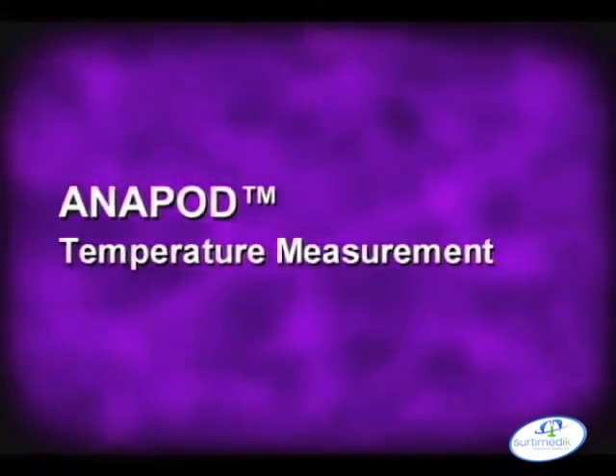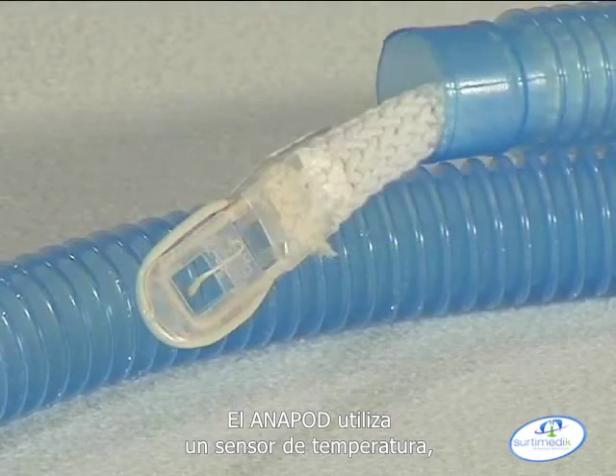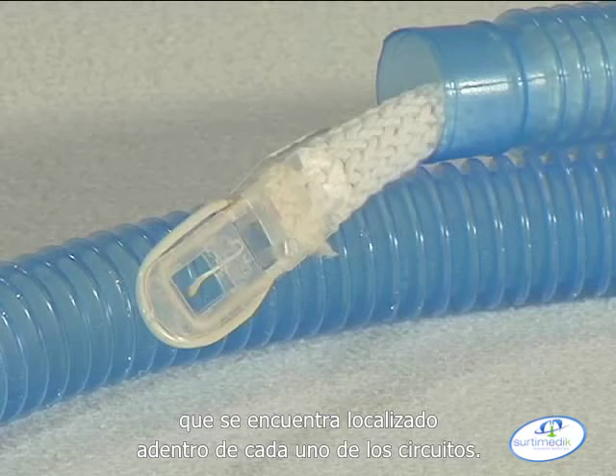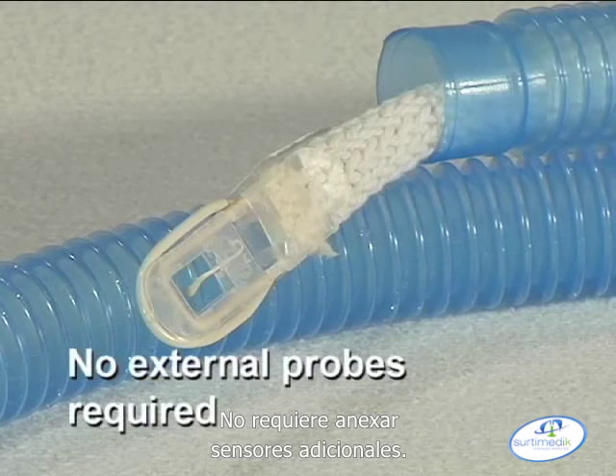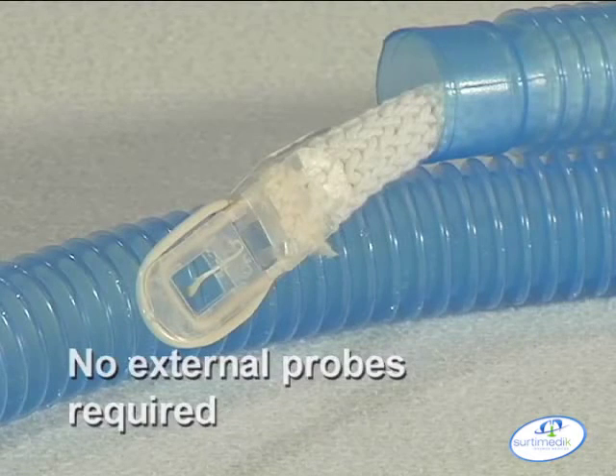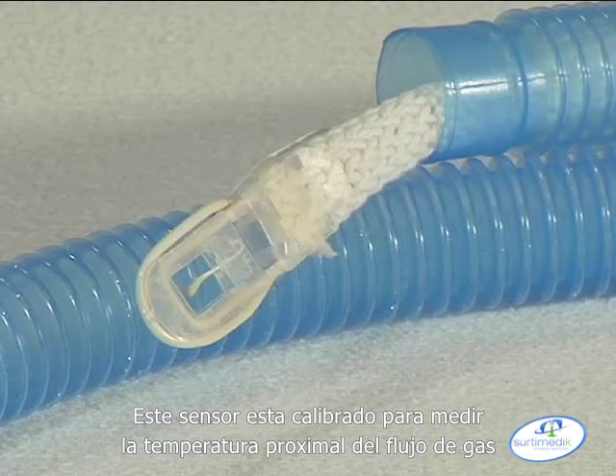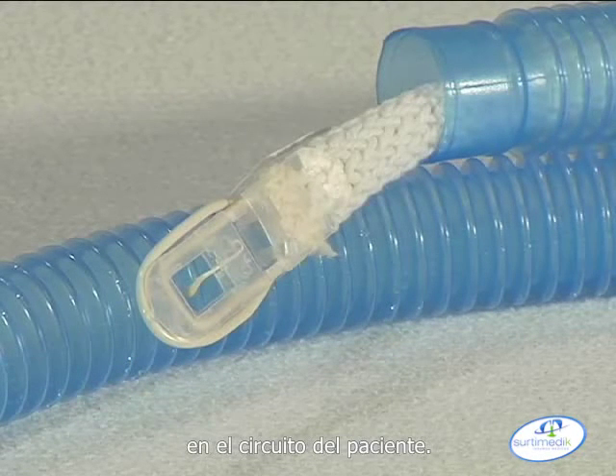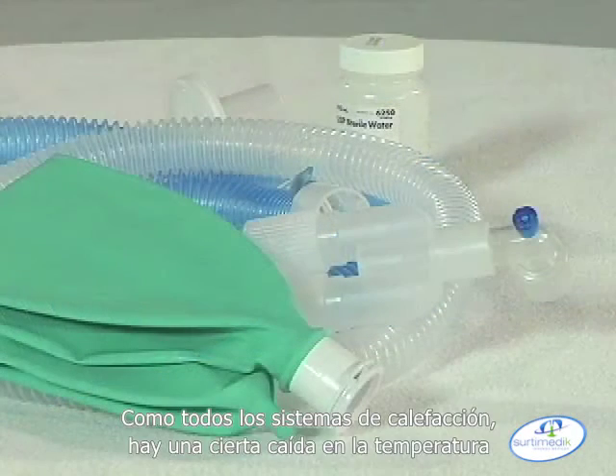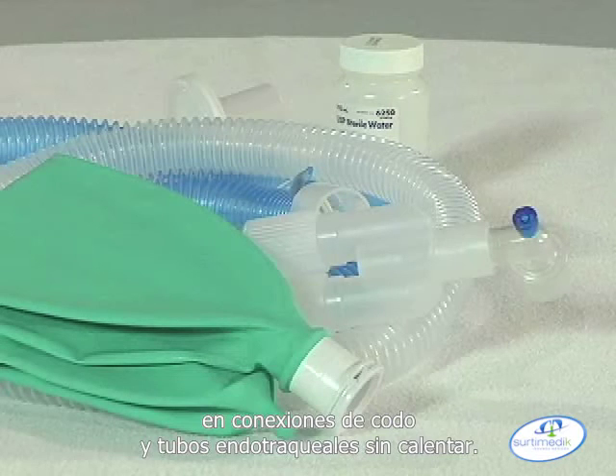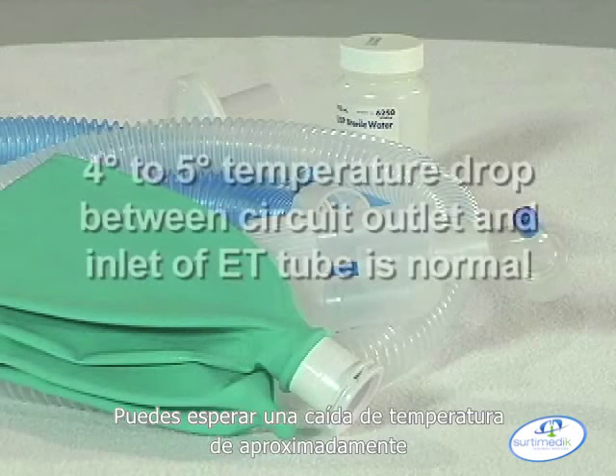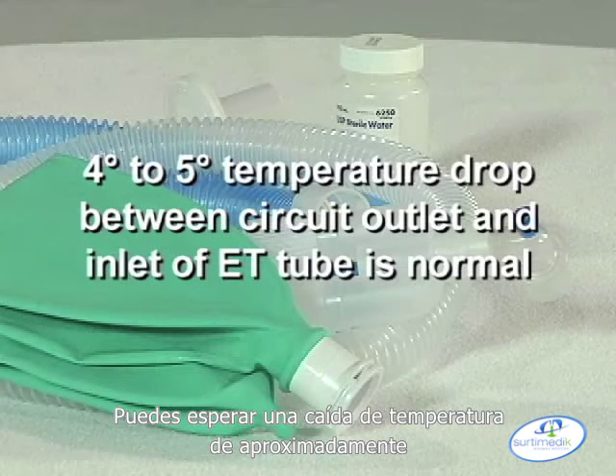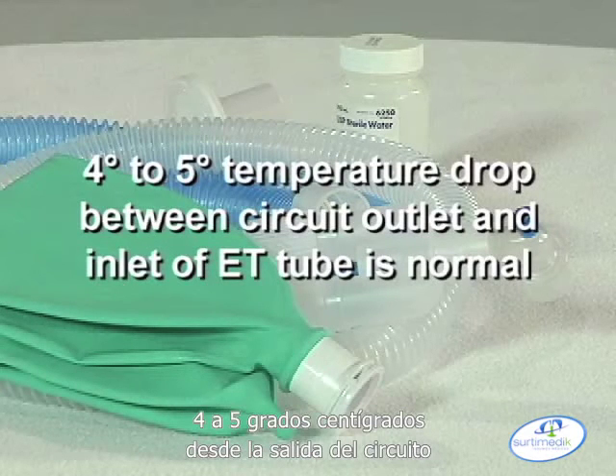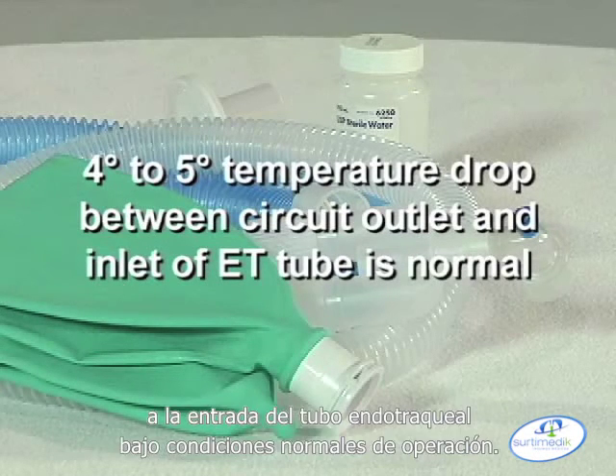Temperature measurement. The Anapod uses one temperature sensor, which is located inside each heated wick circuit. There are no external probes to attach. This probe is calibrated to measure the temperature of the flowing gas at the patient end of the wick circuit. As with all heated systems, there is a certain drop in temperature in unheated Ys, elbows, and ET tubes. You can expect a temperature drop of approximately 4 to 5 degrees centigrade from the wick circuit outlet to the inlet of the ET tube under normal operating room conditions.